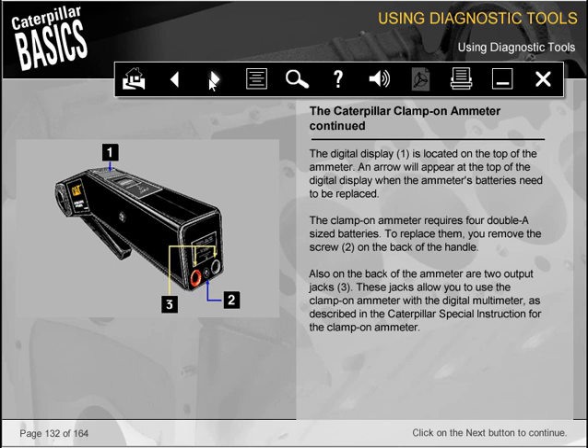The digital display, 1, is located on the top of the ammeter. An arrow will appear at the top of the digital display when the ammeter's batteries need to be replaced. The clamp-on ammeter requires 4 AA-sized batteries. To replace them, you remove the screw, 2, on the back of the handle. Also on the back of the ammeter are 2 output jacks, 3.